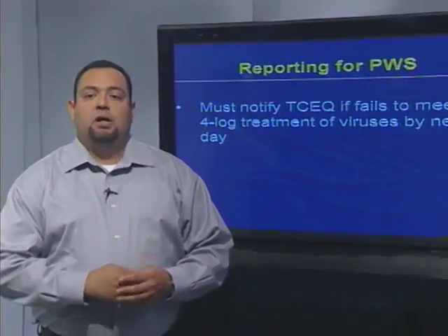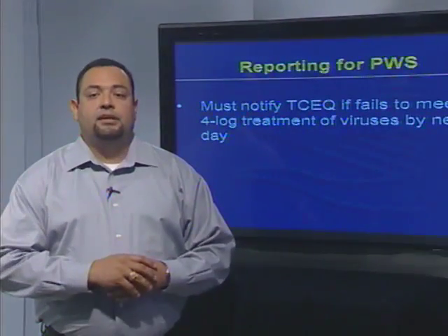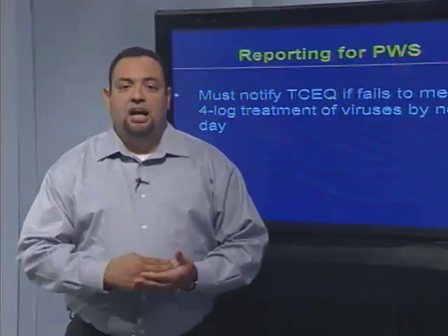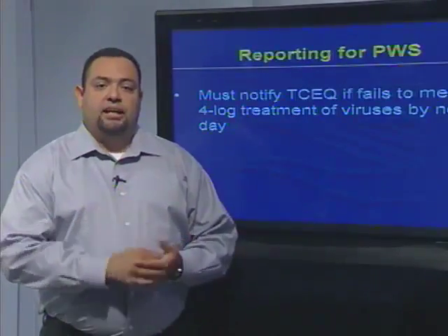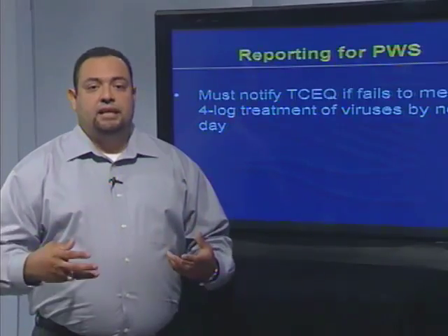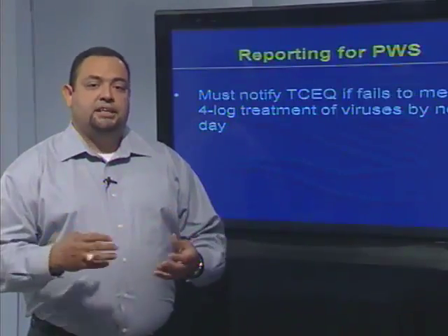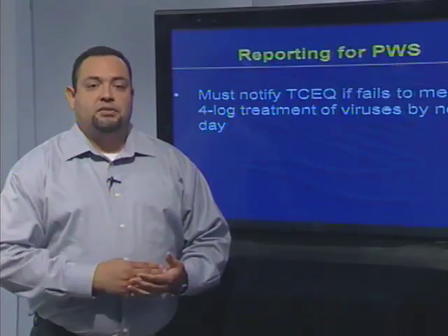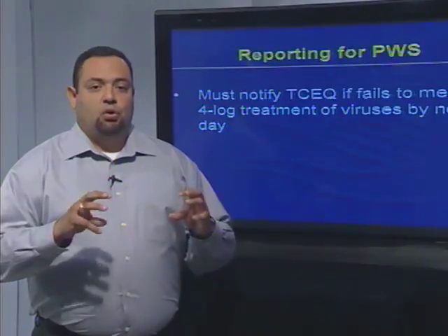And here are the reporting requirements that I talked a little bit about earlier: you must notify TCEQ within 24 hours if you fail to meet the 4-log treatment of viruses. This is very important because water systems typically are not going to get a treatment technique violation if you're using the sheet to obtain the template that Jack is going to talk about. If you use that to calculate your MSR, your minimum specified residual, that is based on the worst case scenario.